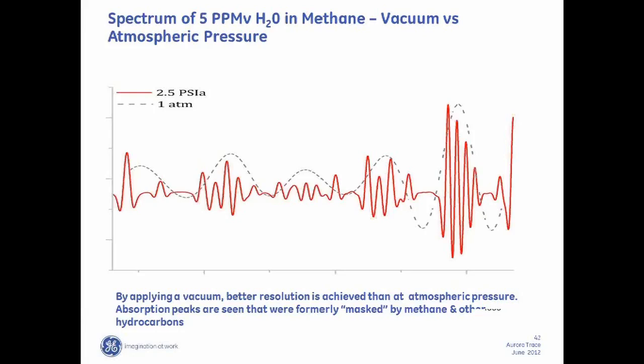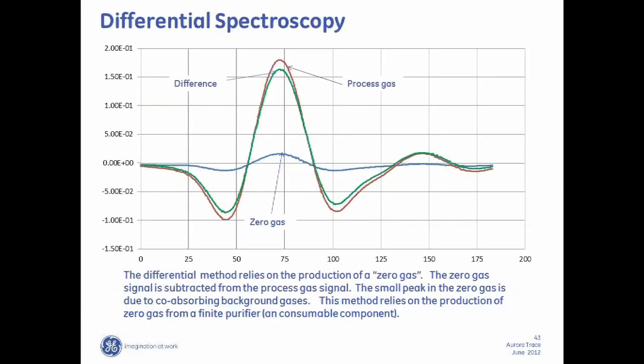Another method of doing that is differential spectroscopy, where you take the gas sample and dry it through a getter or a zero gas generator, a drying system, and you essentially subtract the effect of the zero gas from the process gas. But that bump, or that peak on the zero gas, is ambiguous. Where is that peak coming from? Is it water, or is it due to co-absorbers? You can never know.